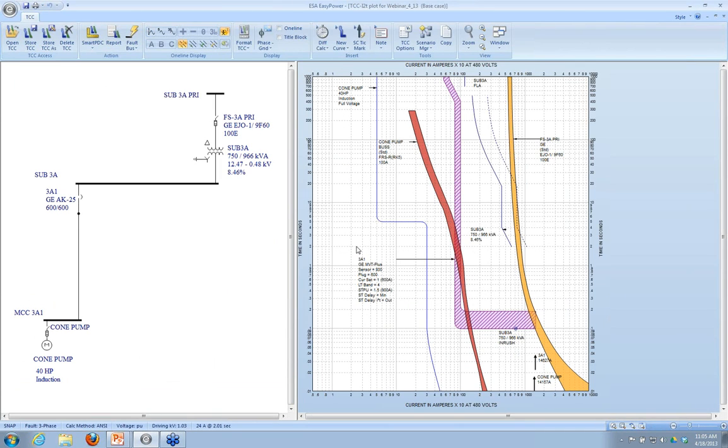So I kind of stacked the deck here a little bit, but here's a fuse down here on this motor starter. This is the red guy, and then this is my short time trip on this GE breaker, a MicroVersaTrip Plus, right? So right now, you can see down here the I2t delay is out, so it's off. This is the normal short time delay. It's just a constant delay above a certain pickup level, which is this value here.